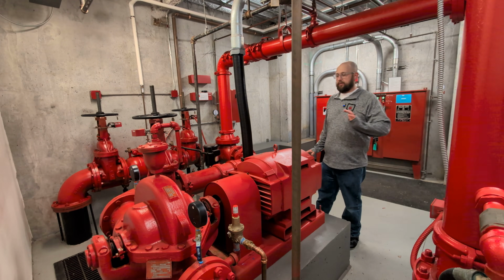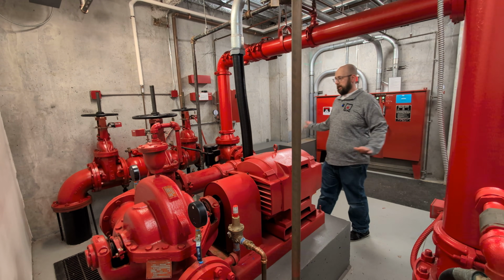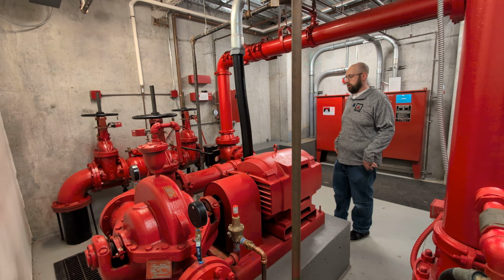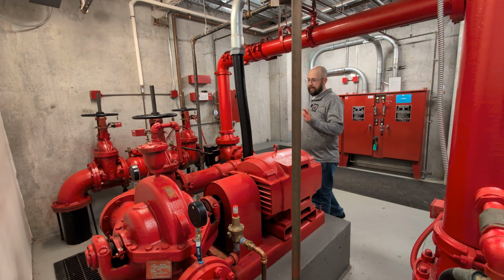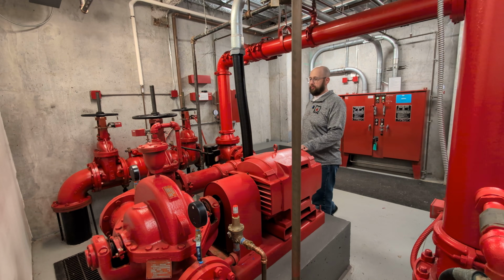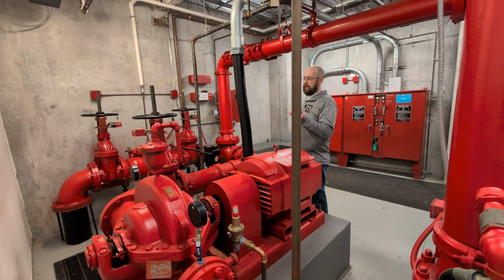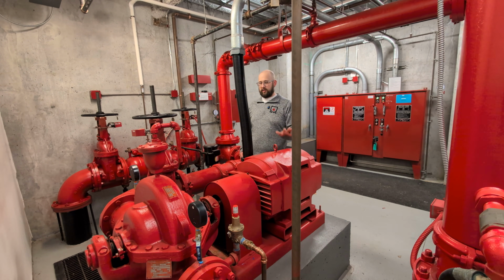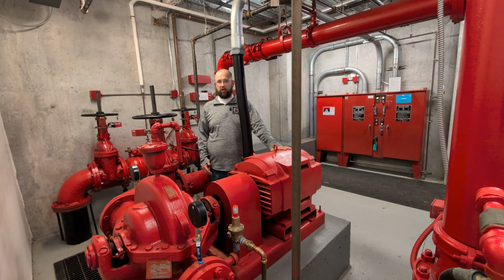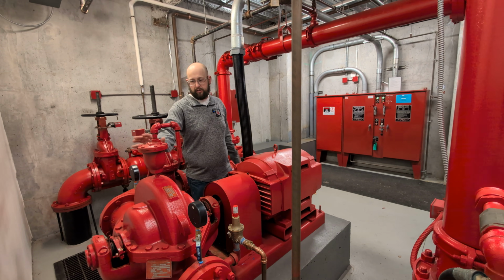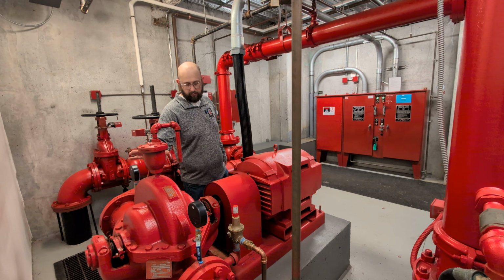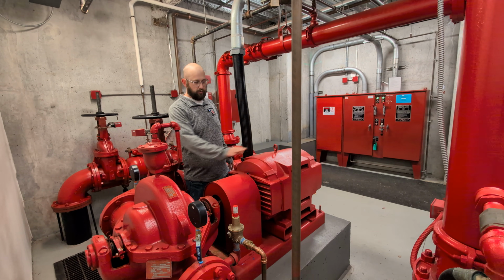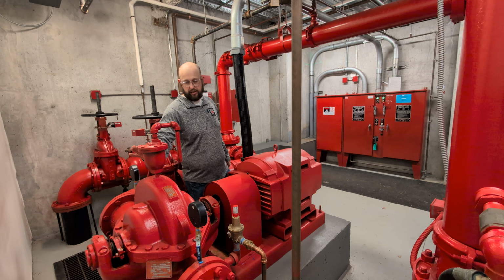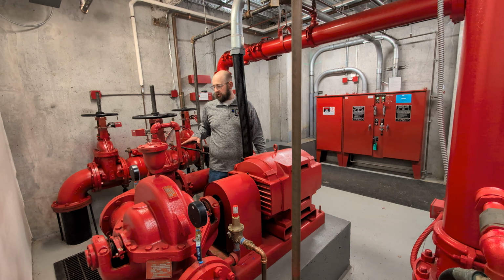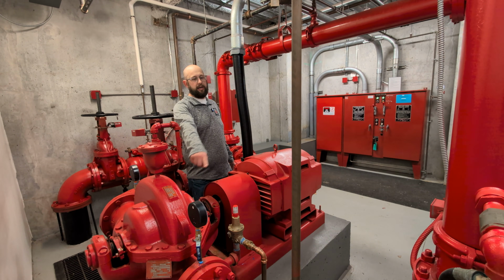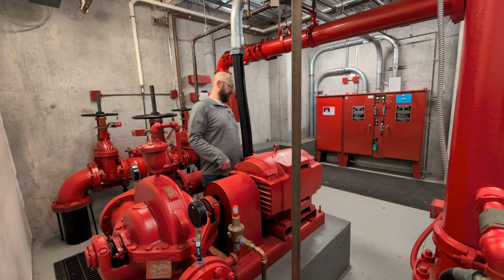All right, before we get into some of the questions, I just want to set the stage, kind of introduce what we're looking at before we start going over some of the questions that you all submitted. We're in the fire pump room. As we said before, this is an electric fire pump. So we've got the fire pump assembly, which consists of the motor itself. This is the electric motor that drives the fire pump. This is the fire pump. This is a horizontal split case fire pump. So we've got the motor, which is coupling up to the pump. We've got our suction side, which is the water going into the pump, and our discharge side, which is the water going out of the pump.